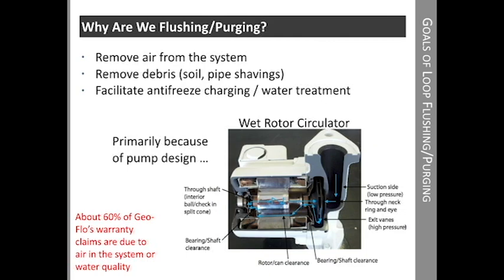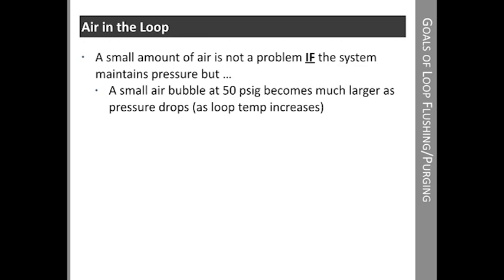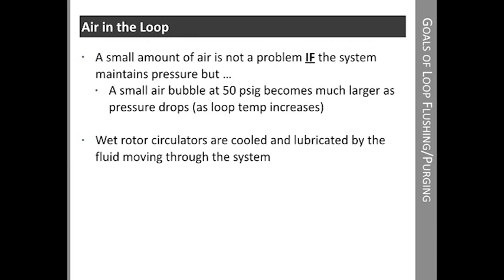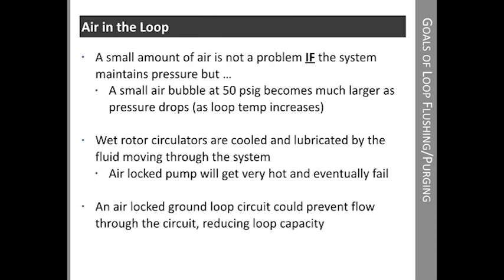Purging the system of air and flushing the system of debris is very important. A small amount of air in the system is not a problem if it's under pressure, but a small bubble at 50 psi becomes much larger as the pressure drops, which occurs as the pipe expands when the loop temperature increases. Wet rotor circulators are cooled and lubricated by the fluid moving through the system. The larger bubble could certainly air lock a pump. When the pump is running dry, it gets very hot and will eventually fail. A ground loop circuit could also become air locked, preventing flow through the circuit and reducing loop capacity. The lack of flow through one of the circuits will act like a smaller loop and could result in a hot or cold loop.